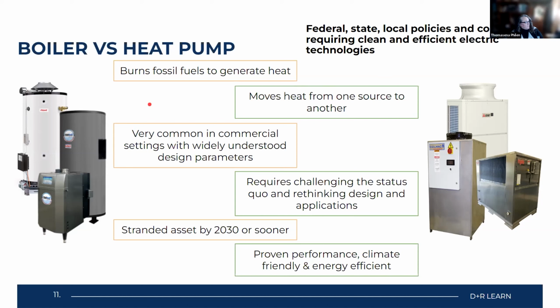So, but boilers burn fossil fuels to generate the heat. But heat pump water heaters move heat from one source to the other, just like any heat pump would. It's moving heat from the air and putting it into the water. And that's not the only type of heat pump water heater that's available, but I only have 20 minutes. So the benefit of going with the boiler is that it's very common in commercial settings with widely understood design parameters. And so engineers, developers, they know what they're getting when they decide to go with a boiler.